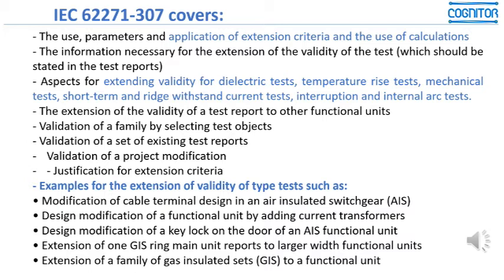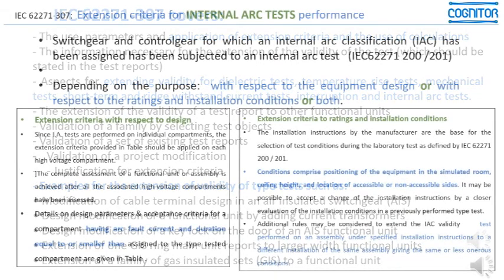Another example: the design modification of a functional unit by adding current transformers, or the design modification of a key lock on the door of an AIS functional unit. Suppose you improve the key lock on the doors to avoid the effects of internal arcs — you are doing a modification, and the user may not have a clear view of whether the additional rules may be considered to extend validity.